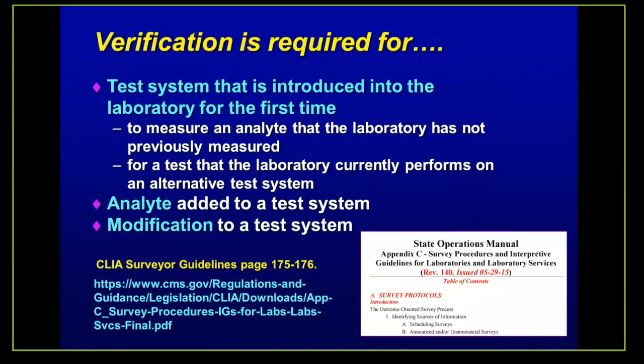Verification is required for any test system that is introduced into the laboratory for the first time. This includes when we need to measure an analyte that the laboratory has not previously measured, and it also includes a test that the laboratory currently performs on an alternative test system.